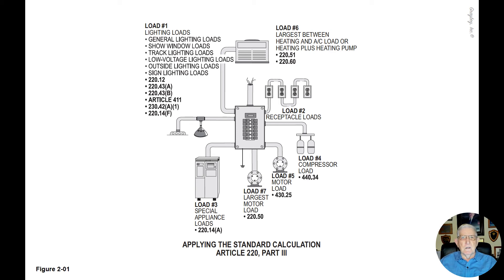Load number 4, we divide the compressor loads into their own group of loads and we take those loads at 100 percent.